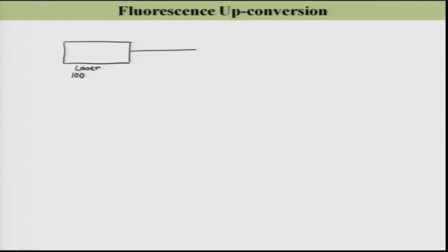Now, let us proceed. Let me draw a setup here. This is my laser, which can generate a very short light pulse, because my aim is to have an instrument response function on the order of 100 or 200 or 300 femtosecond. Obviously, if you use a light pulse of 200 picosecond, then the instrument response function cannot be 100 or 200 femtosecond. So, you have to use at least a 100 femtosecond light source. So, let me take this as a 100 femtosecond pulse it can generate.